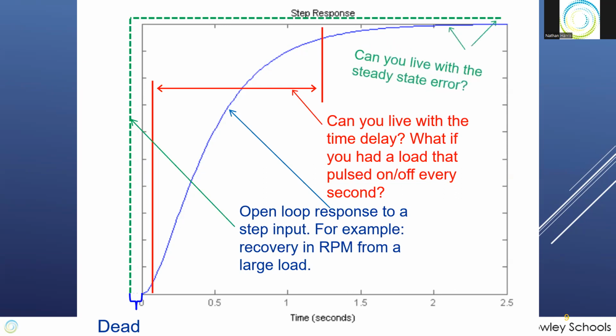And then also, can you live with a steady state error? Now, for a long time, the system today still exists on about a 4% droop. That is, as you draw more power during the day, the frequency comes down, and it's the utility's job to average the frequency out over 24 hours to keep clocks in sync. That was their job for a long time. Well, now clocks are digital, not such a big deal. Computers are much more forgiving of frequencies than they used to be.